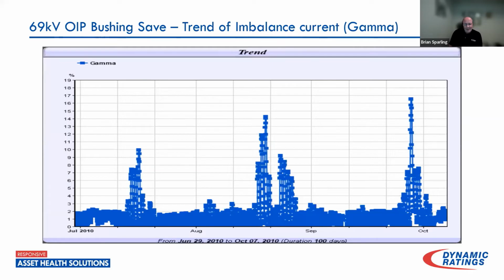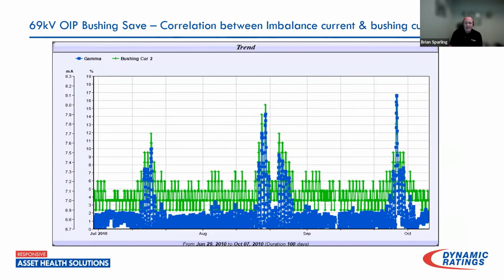When you look at trending of the same data that you just saw in that polar plot, here we see up the left-hand side of the scale the summation of the leakage current over time. And we're seeing changes in the leakage current over time. And the big question is, well, why is this happening? And it turns out that there's a relationship between the top oil temperature of the transformer, which of course is surrounding the base of the bushing, and leakage current, if there is a defect beginning to happen inside the bushing insulation. So we call this a temperature imbalance current. And every time the temperature, in this case you see the green, goes above, I don't have the scale, but every time the temperature did increase, the leakage current as well increased. When it went back down, then the leakage current went back down.